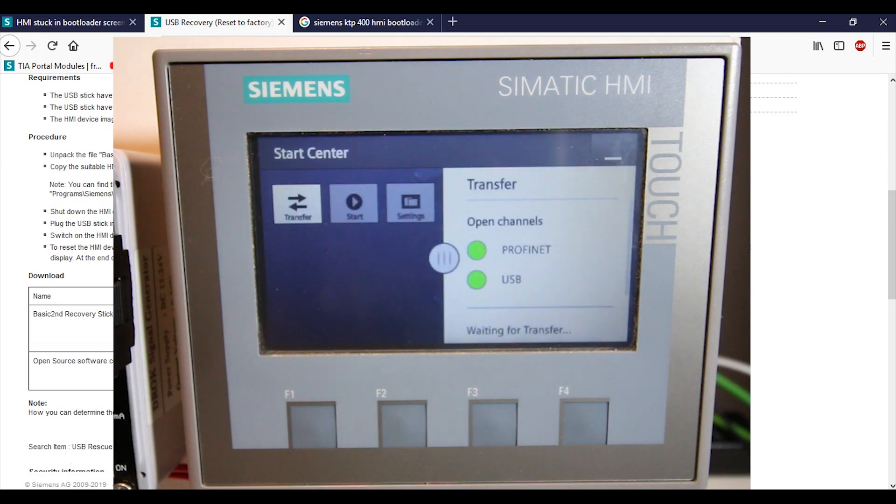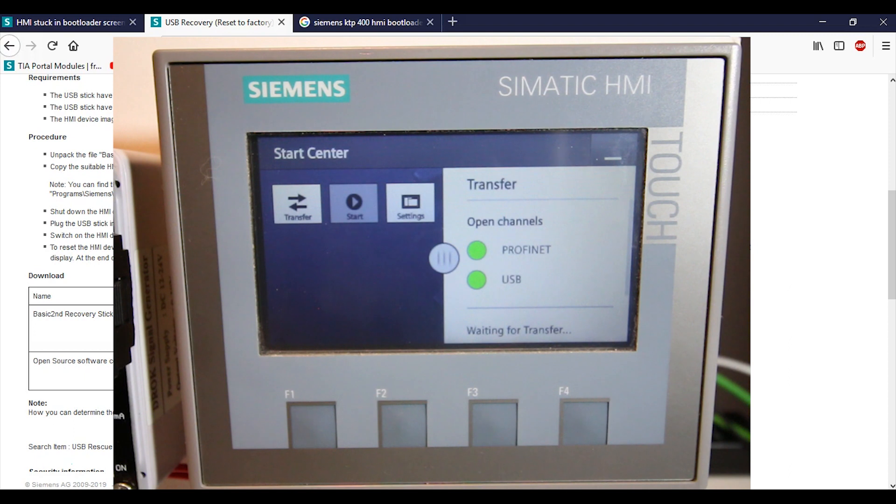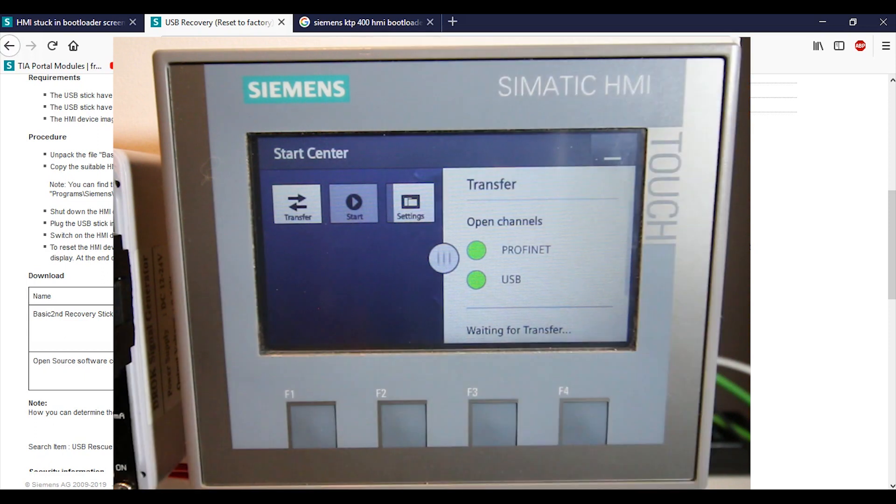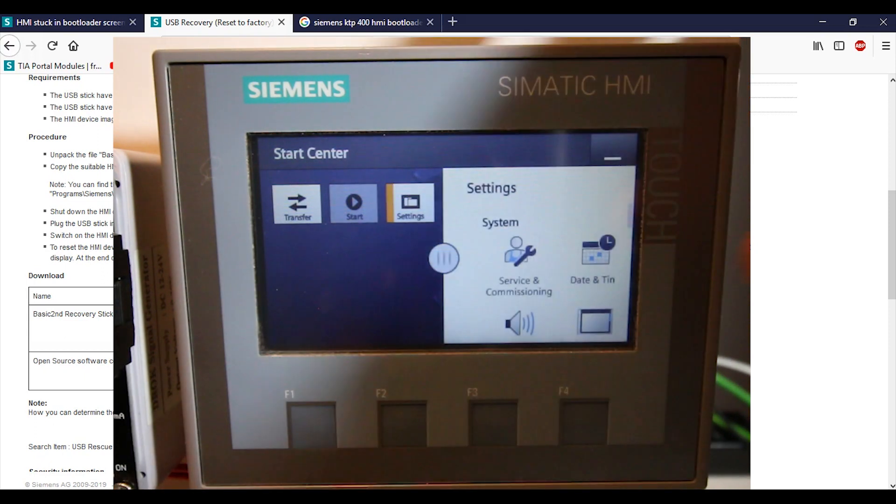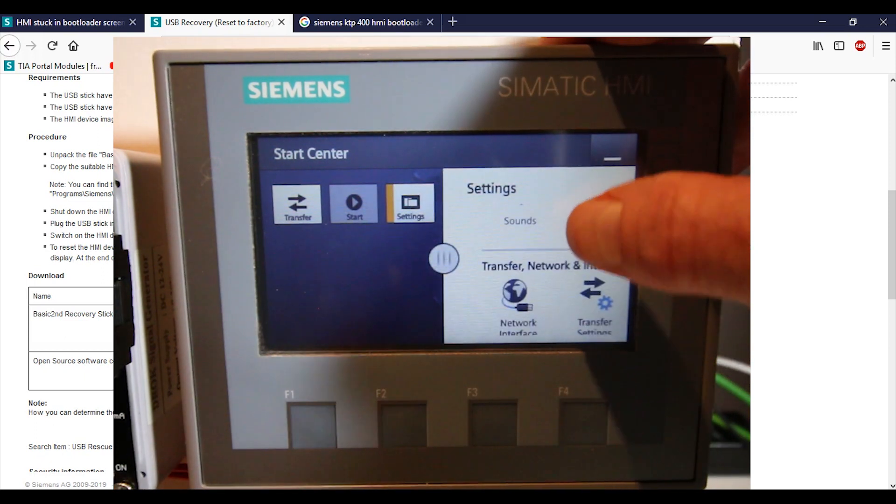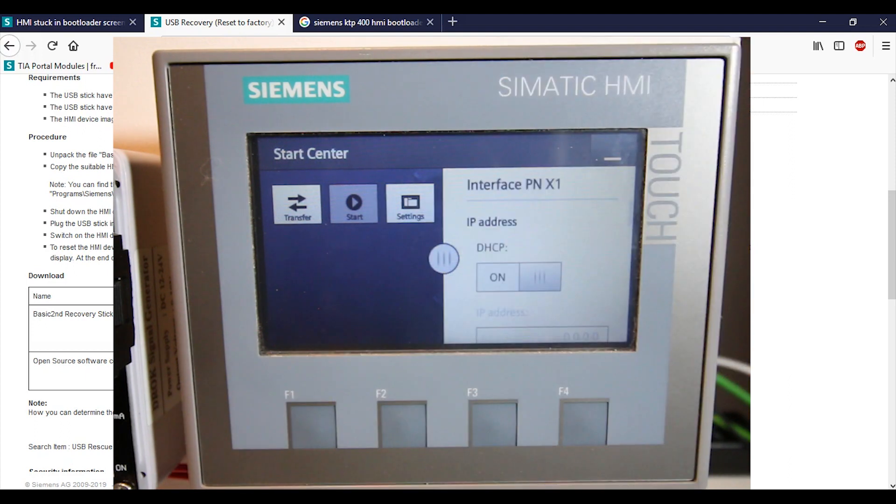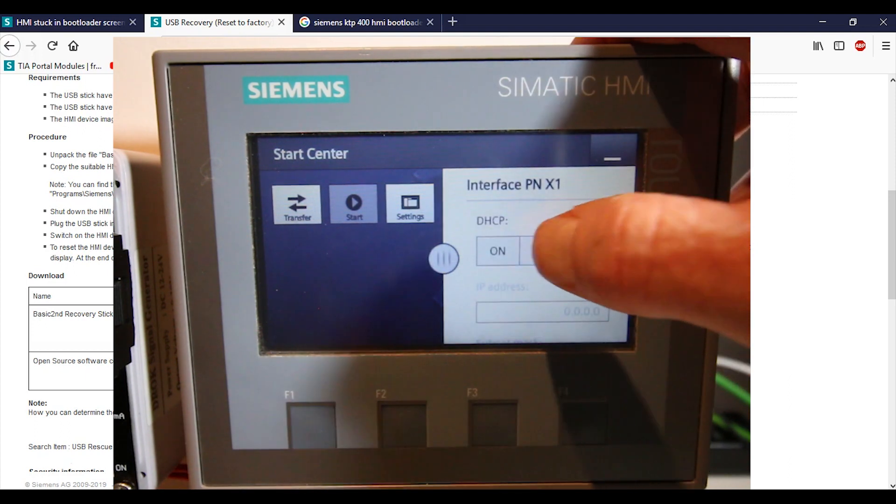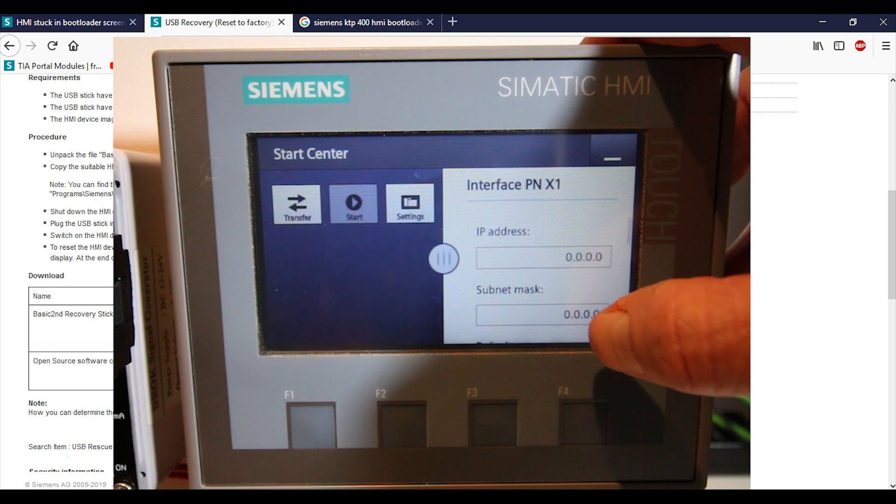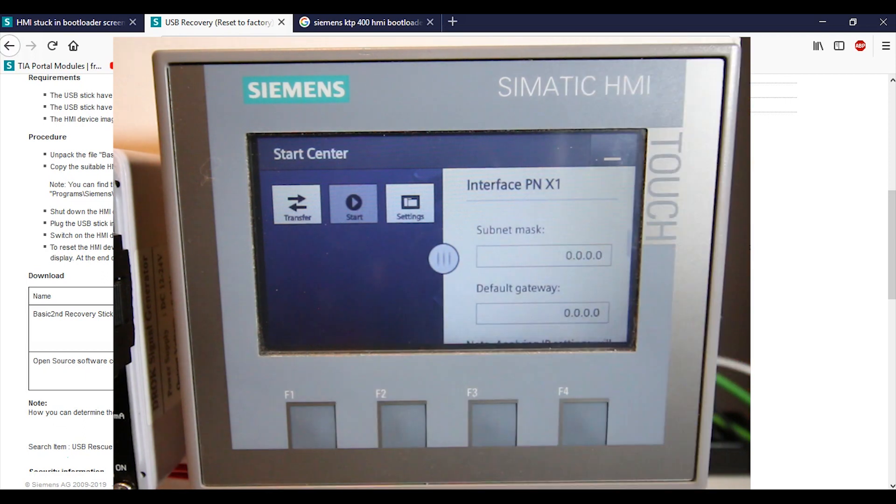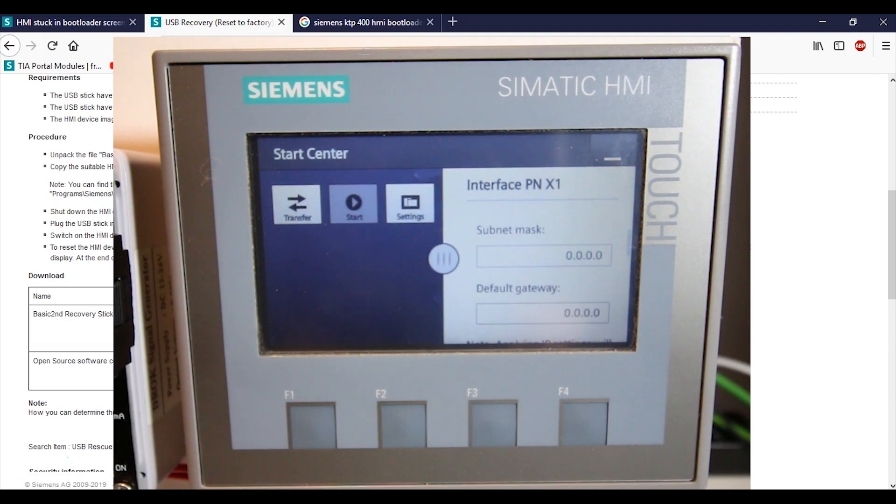Oh, it's gorgeous! Right on. So we're up and running, and now you're able to set your IP again. You're right back to factory settings. You're going to have to go to settings and you're going to have to set your IP and everything. You're going to have to go to network interface and then turn this guy off, and then set your IP, your subnet mask, and your default gateway, and then you'll be able to talk with TIA Portal. Awesome, eh?